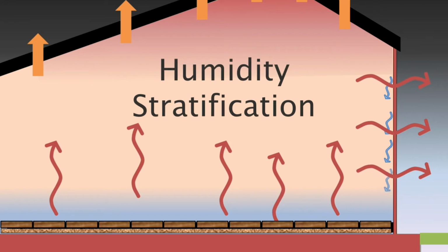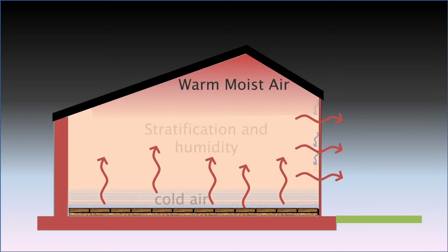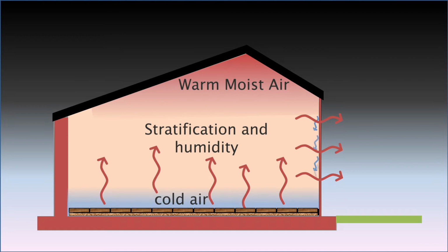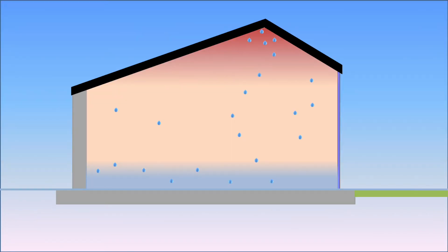With temperature stratification comes humidity stratification. Hotter air has a higher vapor capacity than colder air, so most of the water vapor will be stratified on the ceiling. You do not see it there. You only notice it when that moisture-laden air cools, then falls with the moisture condensing on a cold surface, just like at the bottom of a window. We need to redistribute this moisture more evenly within the air mass.